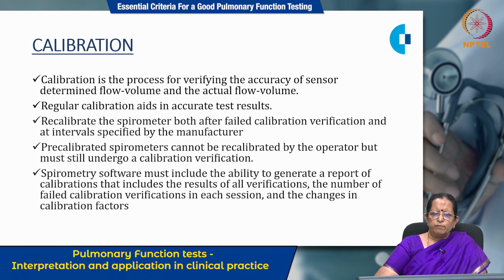Nowadays pre-calibrated spirometers are available, but they cannot be recalibrated by the operator, but must still undergo a calibration verification. Then the spirometry software must include the ability to generate a report of calibrations that includes the results of all verifications, the number of failed calibrations in each session, and changes in the calibration factors.